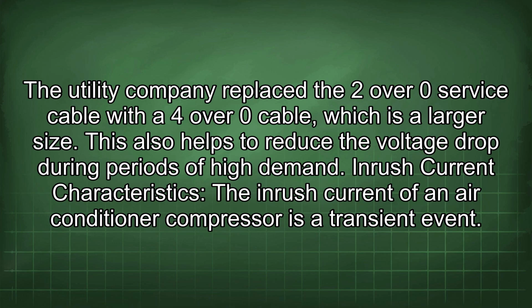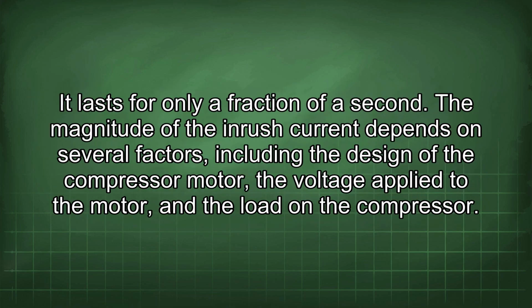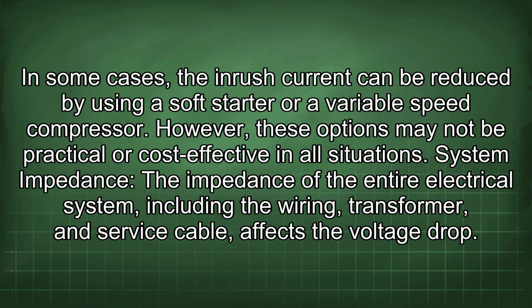Inrush current characteristics. The inrush current of an air conditioner compressor is a transient event. It lasts for only a fraction of a second. The magnitude of the inrush current depends on several factors, including the design of the compressor motor, the voltage applied to the motor, and the load on the compressor. In some cases, the inrush current can be reduced by using a soft starter or a variable speed compressor. However, these options may not be practical or cost-effective in all situations.